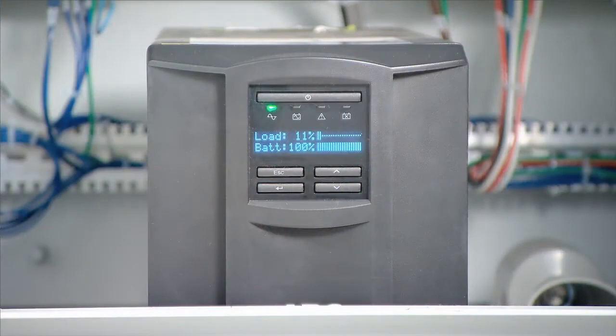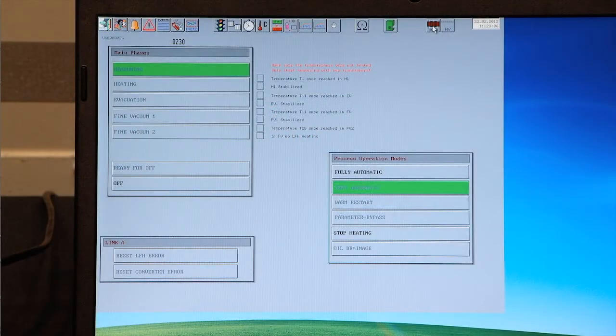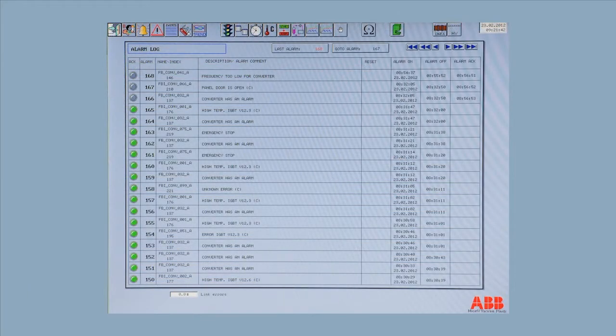Prior to this, make sure that the converter as well as the UPS are switched on at the converter panel. The converter errors are cleared and all components are in automatic mode. Resetting of the alarms in the converter can be made in the lower part of this screen. There is a button that will send the signal to the converter to clear the alarms. Alarms not related to the converter will be reset from the alarm screen.